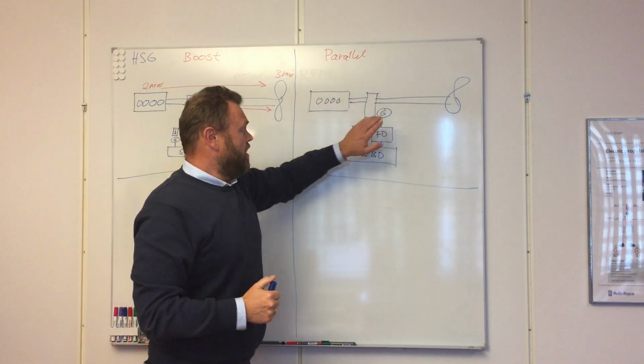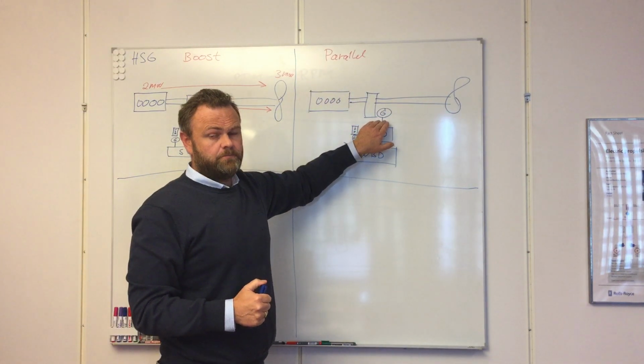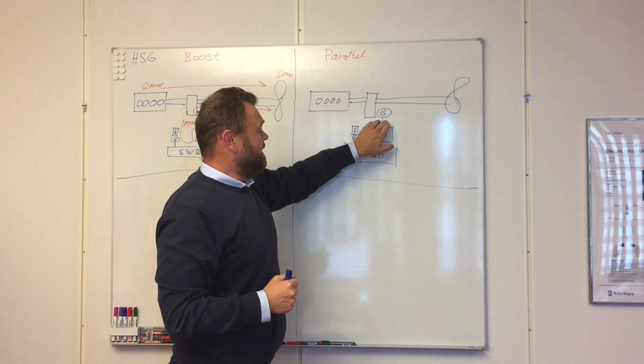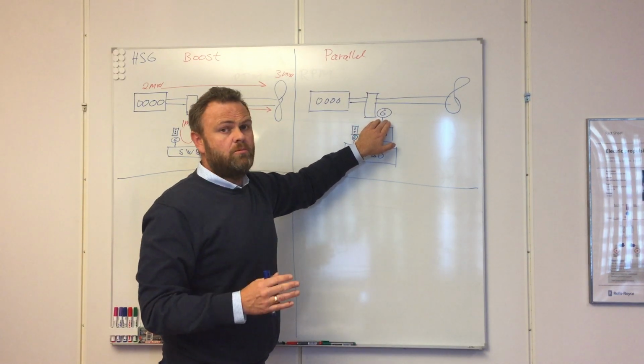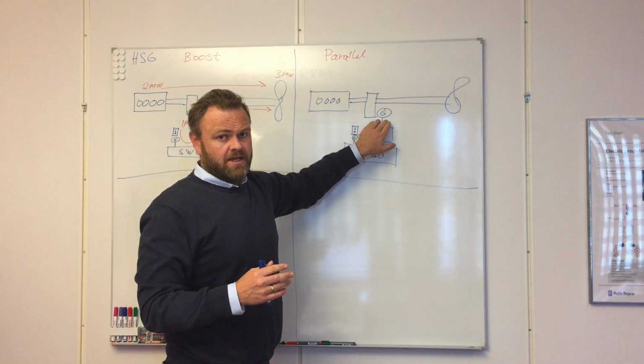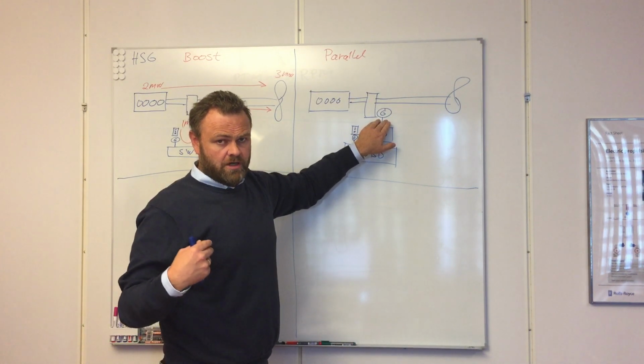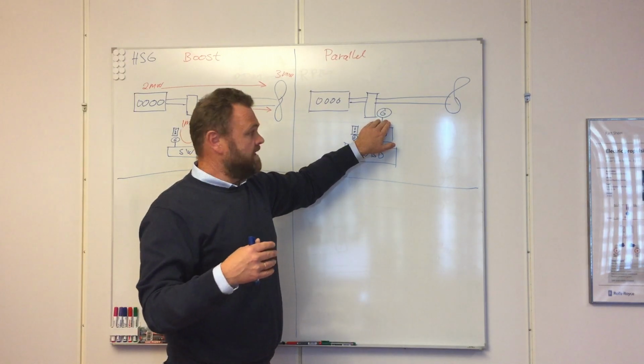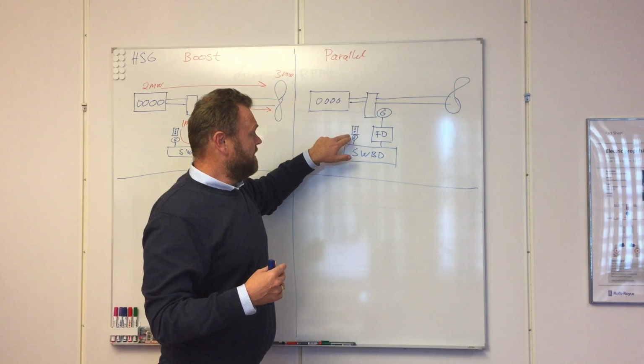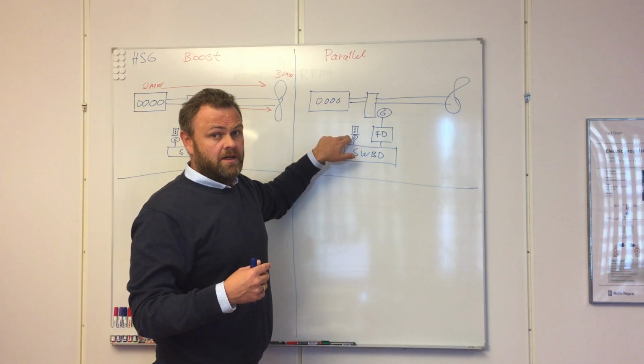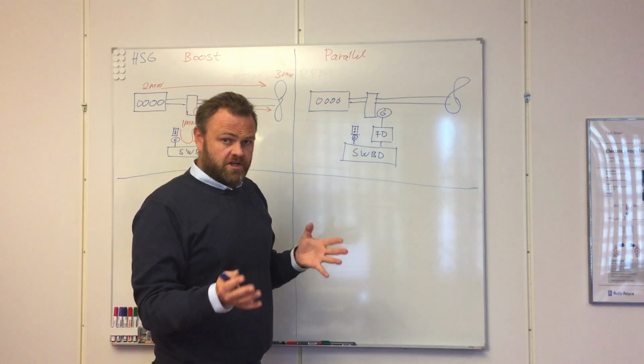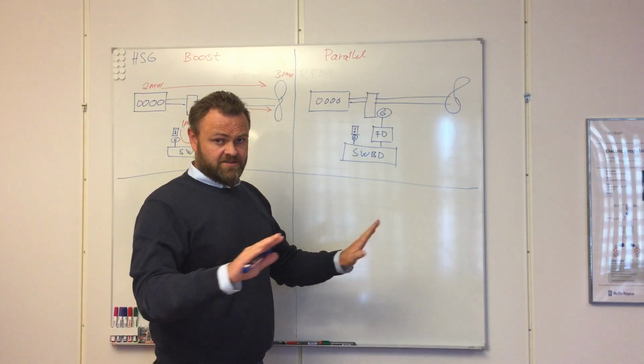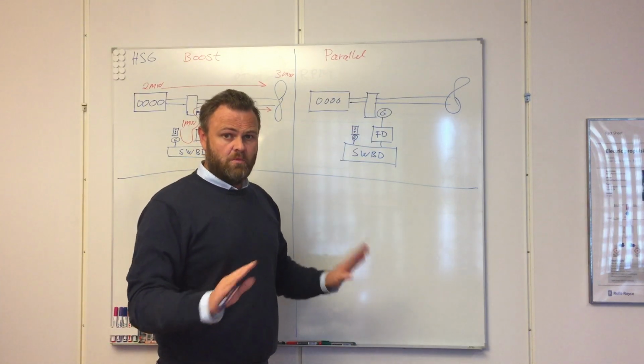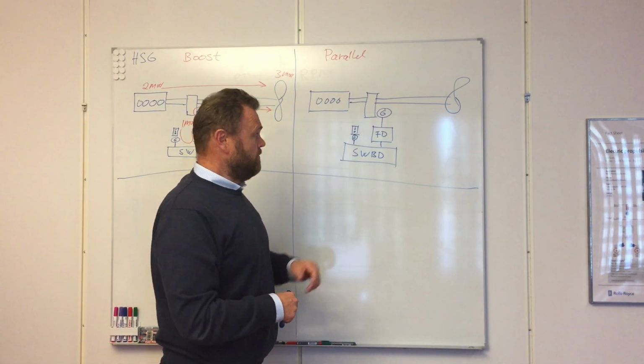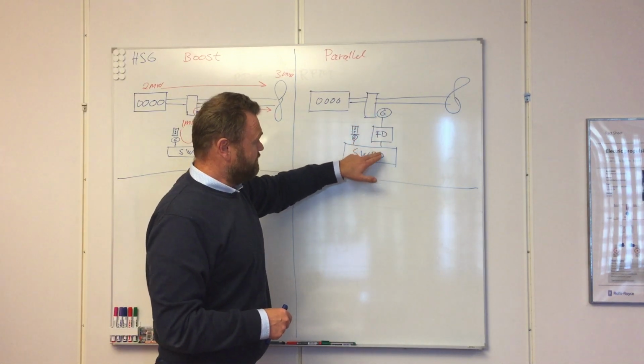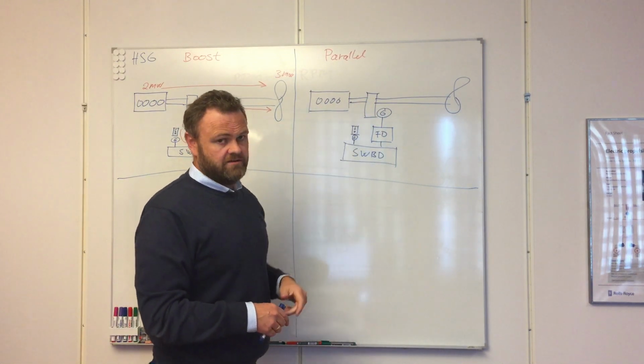It is something you need to know about a shaft generator. And that is in a normal vessel setup, it is not possible to run the shaft generator in parallel with an auxiliary generator. You can do that for short time transfer of load, but not as an operational mode running in hours with the shaft generator running in parallel with the auxiliary generator.